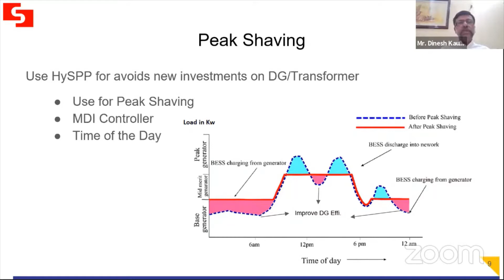Now, what if you could improve the efficiency of your DG? So when the load is low, for example let's say 20%, the efficiency of the DG output is only approximately 20%. So what you do is, at that time, you start charging your battery to move your DG to 80% efficiency. And this is done automatically, programmed once and then done forever. So you improve the efficiency of your DG by charging your battery when the load is low and not charging it when the load is already high.